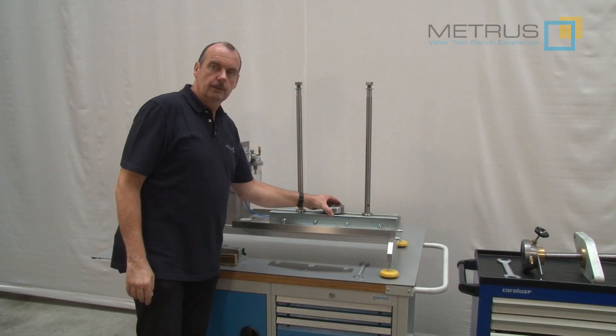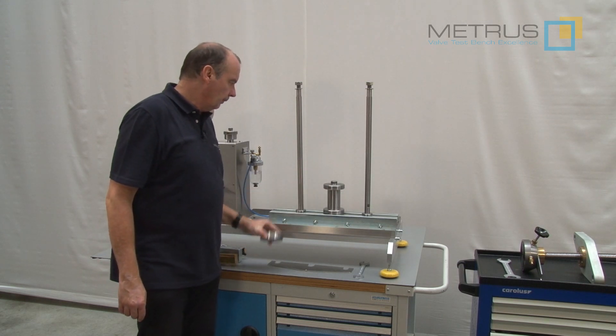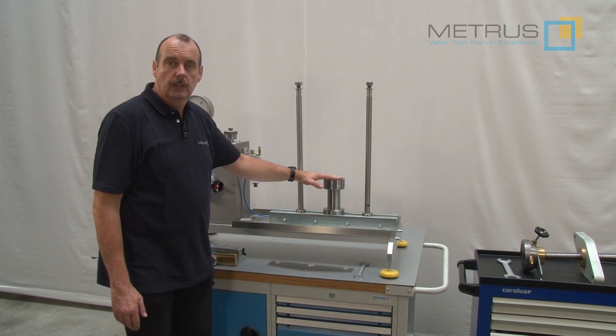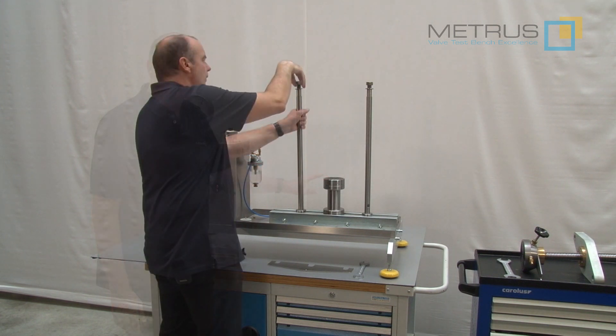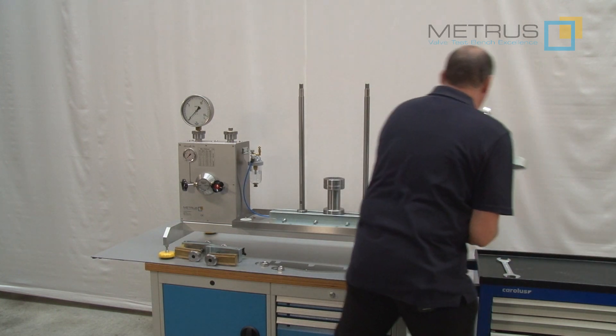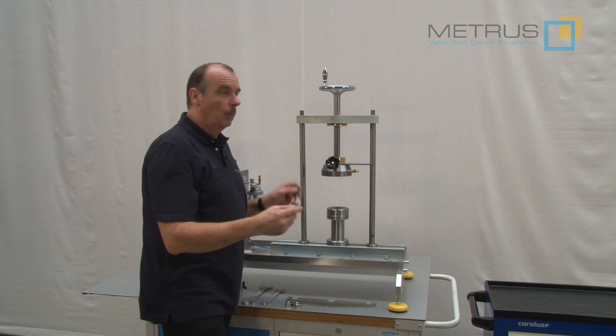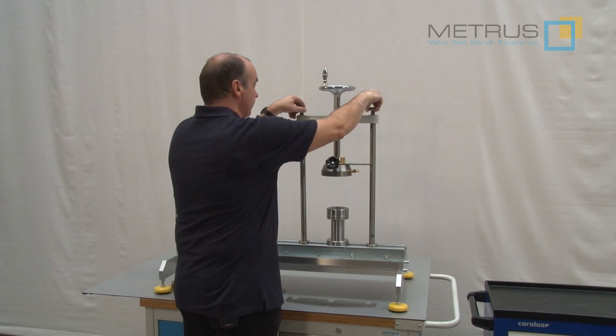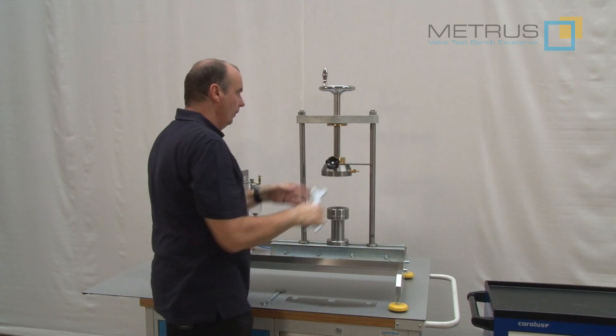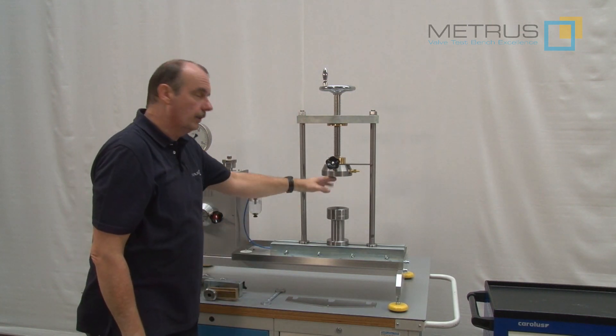Now you can replace the smaller sealing plate, or you can use the distance piece. Put the sealing plate onto the top — this will reduce the length of the clamping, especially when you want to test smaller shut-off or control valves. Remove the nuts of the distance bolts. Take the head beam and place it onto the distance bolts. Replace the washers and the fastening nuts. Tighten these firmly.